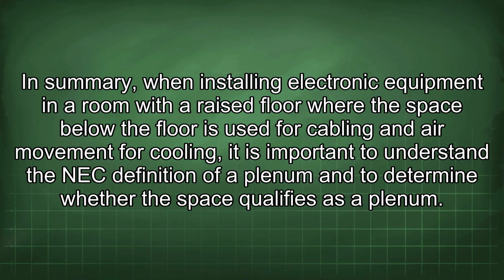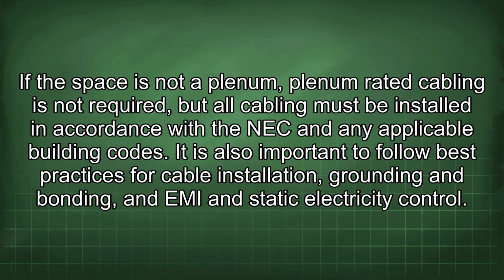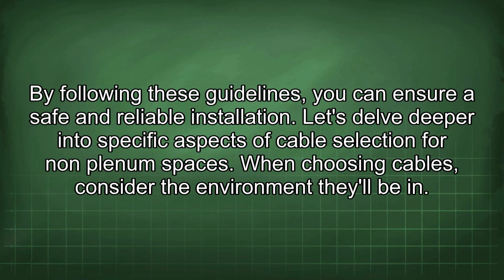In summary, when installing electronic equipment in a room with a raised floor where the space below the floor is used for cabling and air movement for cooling, it is important to understand the NEC definition of a plenum and to determine whether the space qualifies as a plenum. If the space is not a plenum, plenum-rated cabling is not required, but all cabling must be installed in accordance with the NEC and any applicable building codes. It is also important to follow best practices for cable installation, grounding and bonding, and EMI and static electricity control. By following these guidelines, you can ensure a safe and reliable installation.